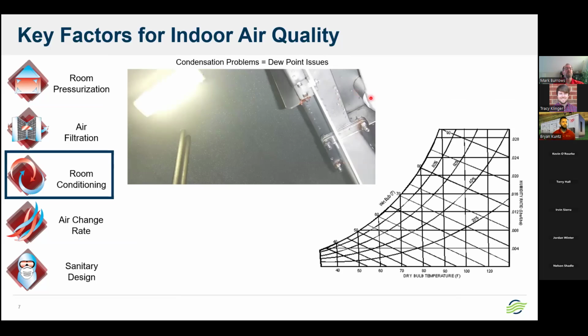Room conditioning. This is super critical, especially as it relates to dew point issues. You can see in the picture here, there are tiny speckles on the ceiling. What's not shown is that this is directly over open product. So as you might guess, every one of these droplets of water could possibly contain bacteria, right? All it takes is one droplet of water to land on open product, and you could have an outbreak of some sort. So we want to make sure we eliminate the possibility of this happening, which really gets into psychrometrics that Mark's going to talk a little bit about today, and how we avoid that.